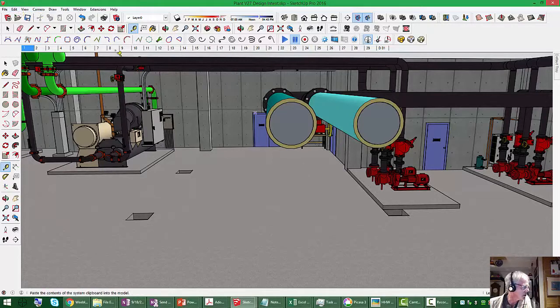I'm just getting rid of the guides that accidentally got put in there. Okay, so we can measure the radius of this pipe, and the radius of the pipe is 6 inches, so that's a 12-inch pipe. Now, if you're doing this a lot, you might already know that a 12-inch pipe is good for quite a bit of flow.